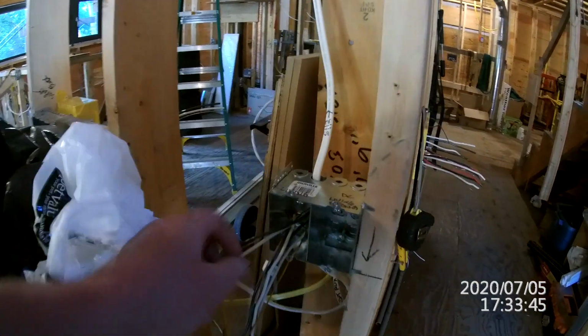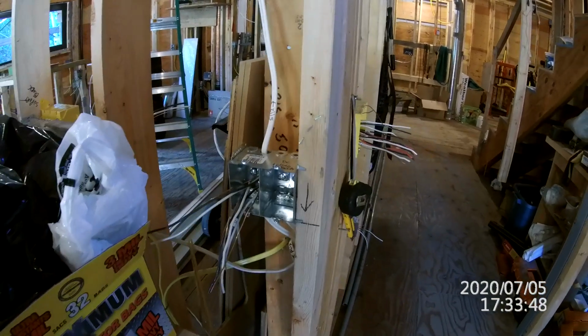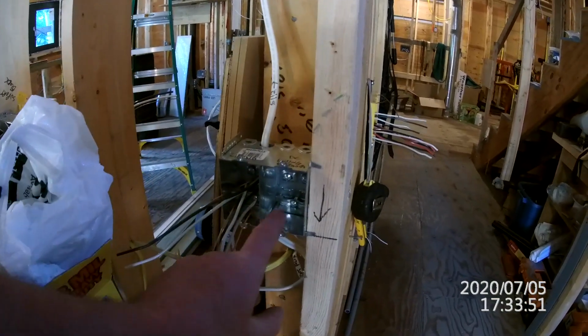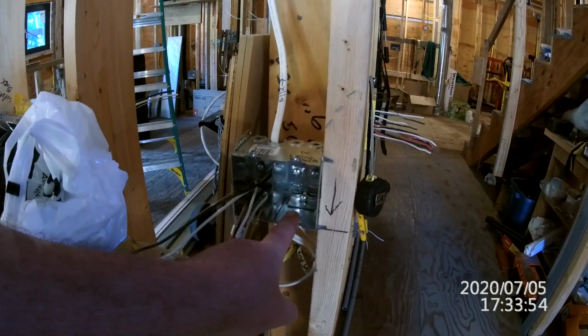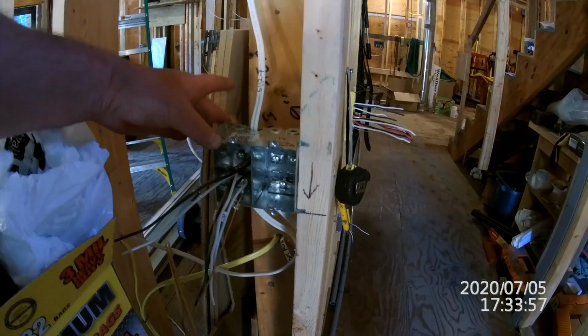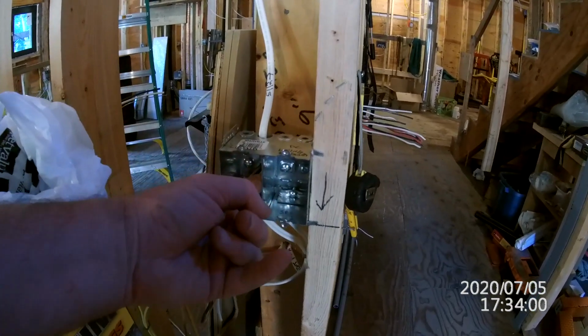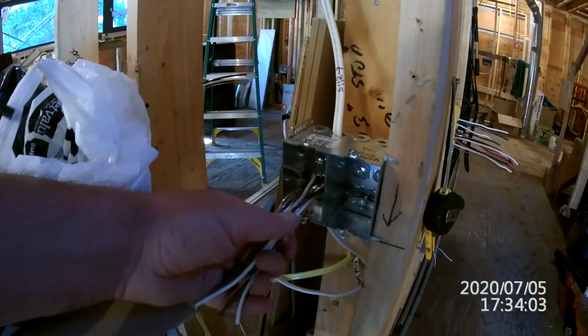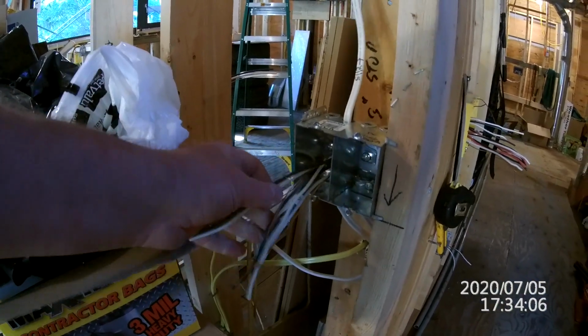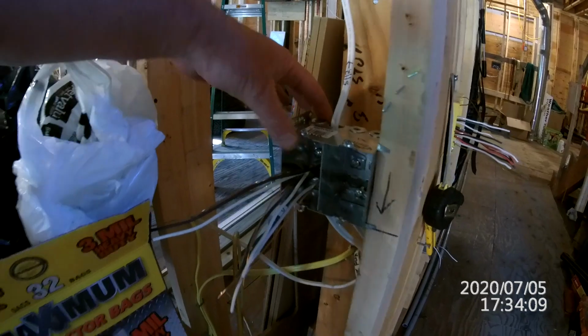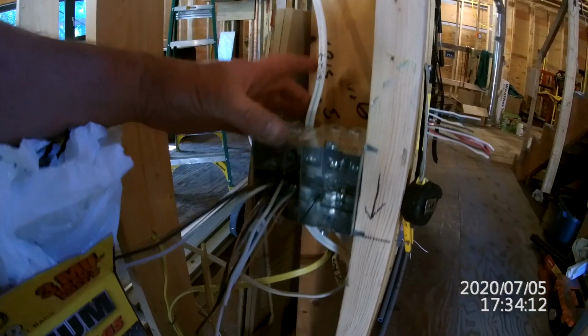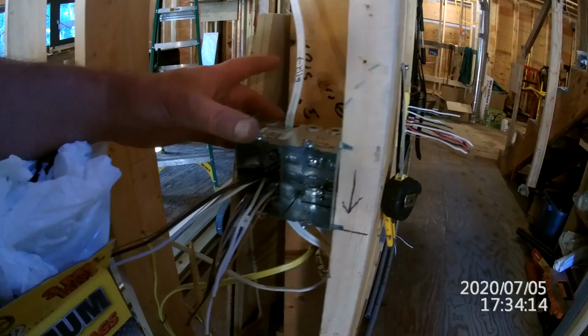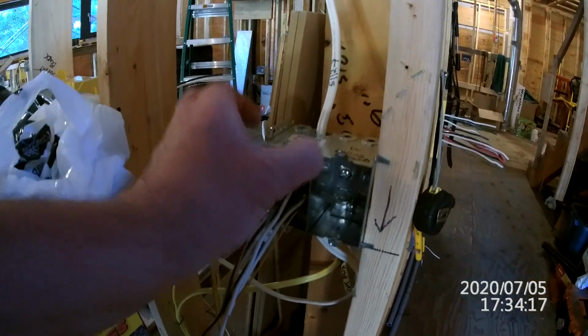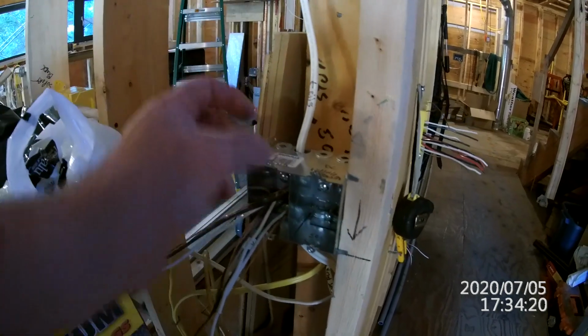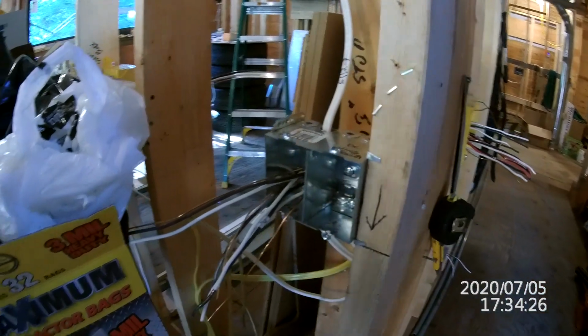The reason this is loose is because step 1, I replaced the 2-gang plastic with this 2.5 inch deep 2-gang metal box and put in this partition plate. But now my box fill on the 110 volt is too high for a single 2.5 inch box, so now I have to step up to a 3 inch deep box, and they only come in gangable boxes, meaning a single gang that you then have to remove a partition plate from and keep joining up if you need multiple gang boxes.